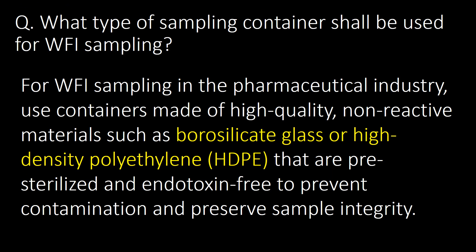A very basic question: what type of sampling container shall be used for WFI sampling? For WFI sampling in the pharmaceutical industry, use containers made of high-quality non-reactive materials such as borosilicate glass or high-density polyethylene (HDPE) that are pre-sterilized and endotoxin-free to prevent contamination and preserve sample integrity.